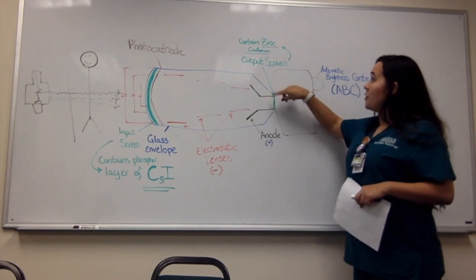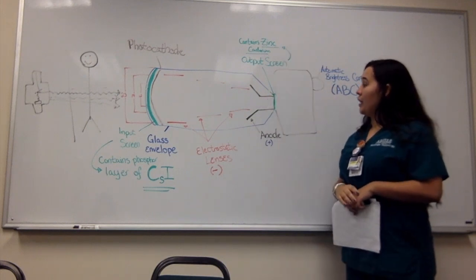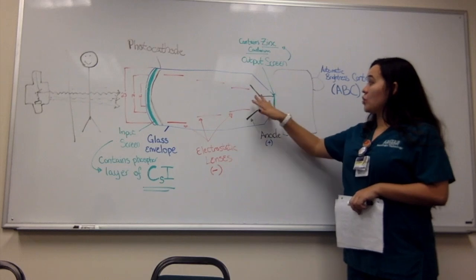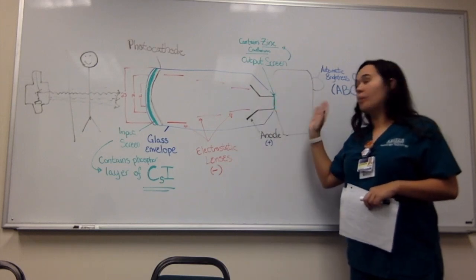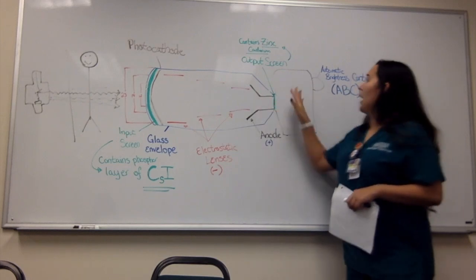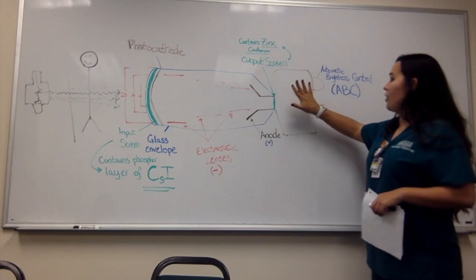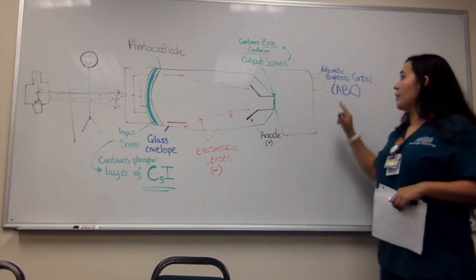The output screen contains a layer of zinc cadmium. This is where the electrons are then converted into light photons once again, and it goes into the tower, which contains automatic brightness controls.